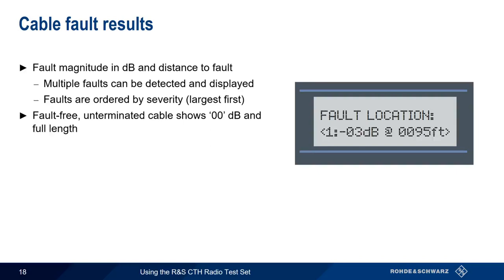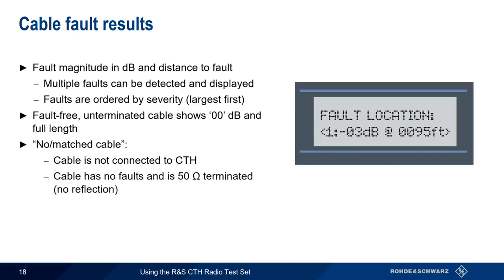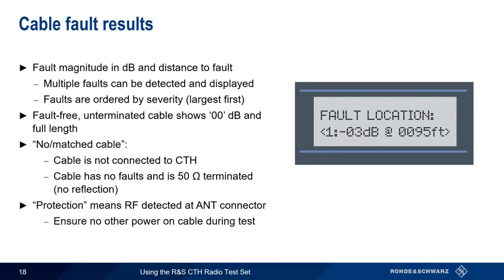There are also two special messages. "No/Matched Cable" means either that no cable is connected to the CTH, or that the cable has no faults and terminates into a pure 50-ohm load — a matched load absorbs all of the transmitted signal, so there would be no reflections. The other special case is "Protection," which means that another source of RF was detected on the cable. In this case, be sure that there are no other sources of RF present on the cable while running the test.